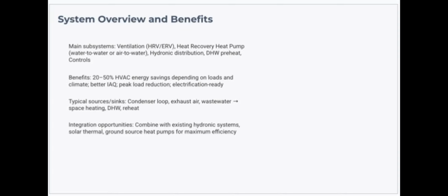The system benefits and main subsystems are ventilation, HRVs and ERVs, heat recovery, heat pump, water to water or air to water, hydronic distribution, and DHW preheat and controls. Like I said earlier, the benefits are 20 to 50% savings for energy throughout the HVAC systems, depending on the load and climate, better IAQ and peak load reduction, and also electrification ready. Typical sources: condenser loop, exhaust air, wastewater, space heating, DHW, and reheat. Integration opportunities: combined with existing hydronic systems, solar thermal, ground source, heat pumps for maximum efficiency.